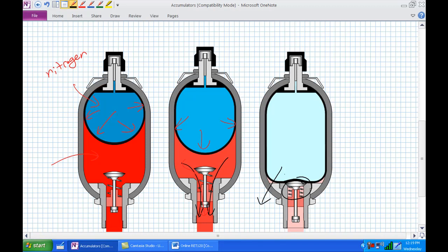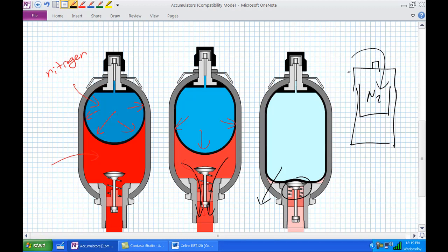That would be totally bad. There's another type of gas-charged accumulator, called a piston accumulator. Think about it: it's a piston face that's charged with nitrogen here, and here's my hydraulic fluid inside here. It moves up and down, very similar to a bladder. It's just got a hard disk there. The reason they have those versus the bladder is sometimes nitrogen can leak through there. So for some critical applications, I'll actually give you an article about this one. It's pretty neat, about piston hydropneumatic accumulators.